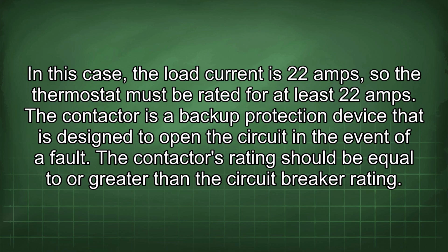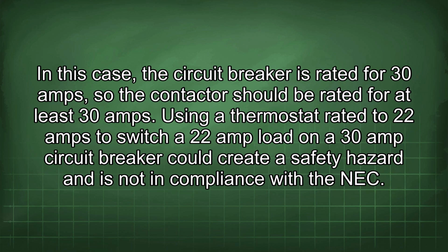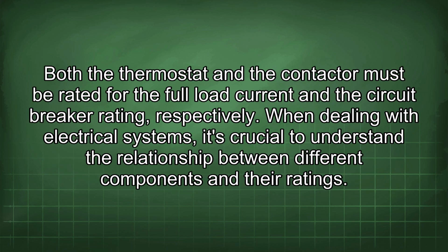fault. The contactor's rating should be equal to or greater than the circuit breaker rating. In this case, the circuit breaker is rated for 30 amps, so the contactor should be rated for at least 30 amps. Using a thermostat rated to 22 amps to switch a 22 amp load on a 30 amp circuit breaker could create a safety hazard and is not in compliance with the NEC. Both the thermostat and the contactor must be rated for the full load current and the circuit breaker rating, respectively.